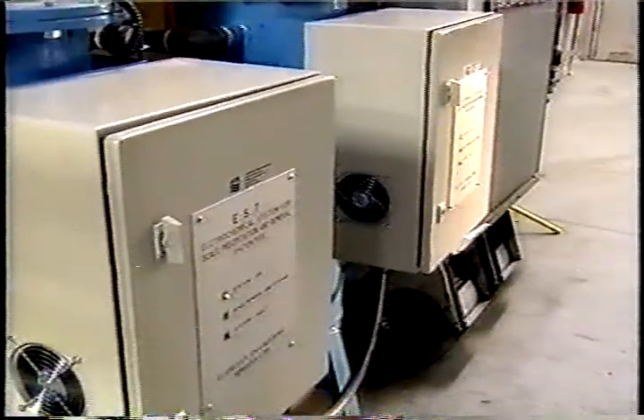Instead, what they have now was developed in Israel, and it uses electrolysis to remove mineral deposits. With this process, it's no longer required that large volumes of water be wasted to maintain the mineral balance within a cooling system. The system was developed in Israel, and the Salt Palace is the second building in the U.S. to use it.